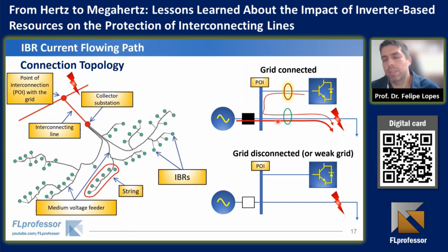So here it is not expected to have a problem. But if the grid is disconnected or a weak grid is considered, the IBR contribution will pass through both lines. And we started to understand that the problems are not limited to the interconnecting line, but rather they can reach the adjacent system. So far, we don't know how many lines can be affected by this contribution, but we know that adjacent lines can be affected. I mean, the protection schemes applied in adjacent lines.